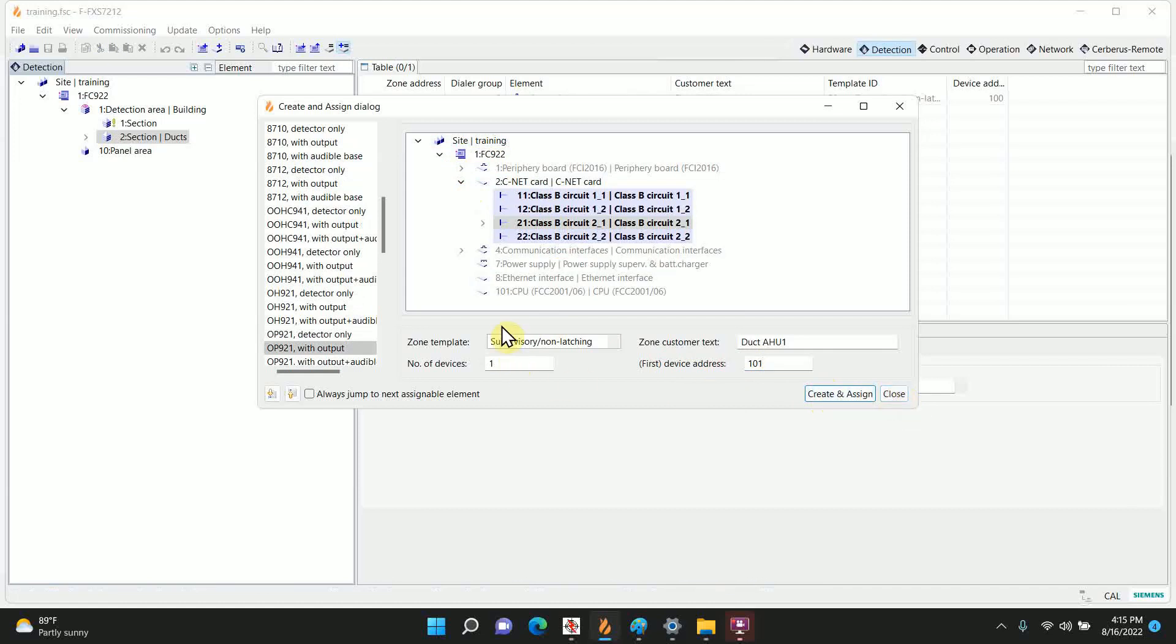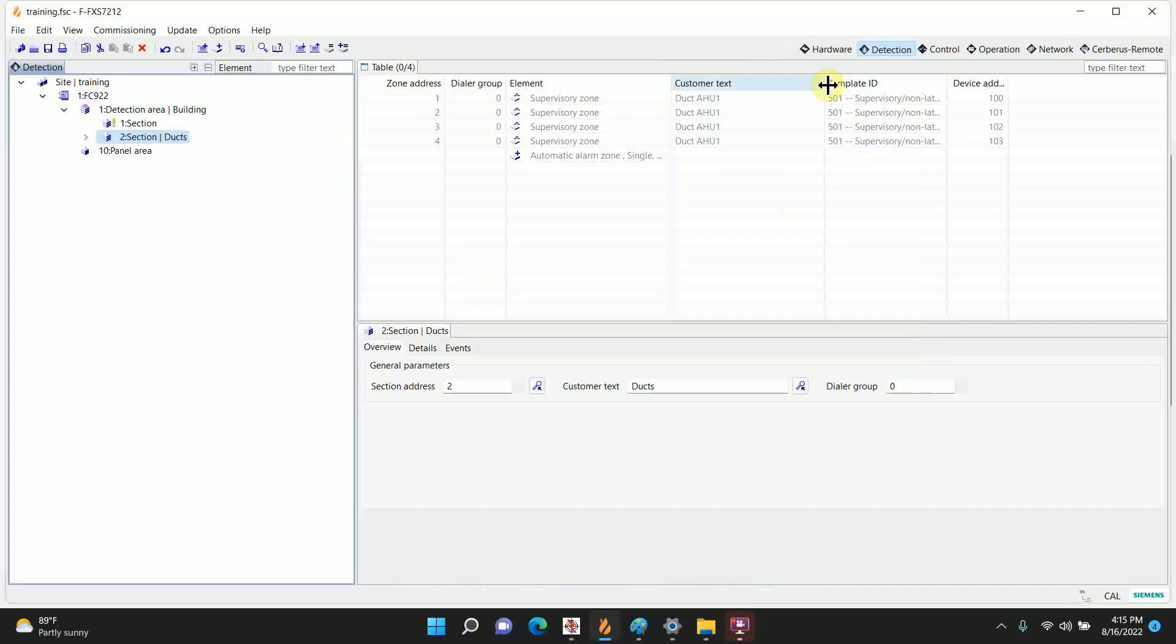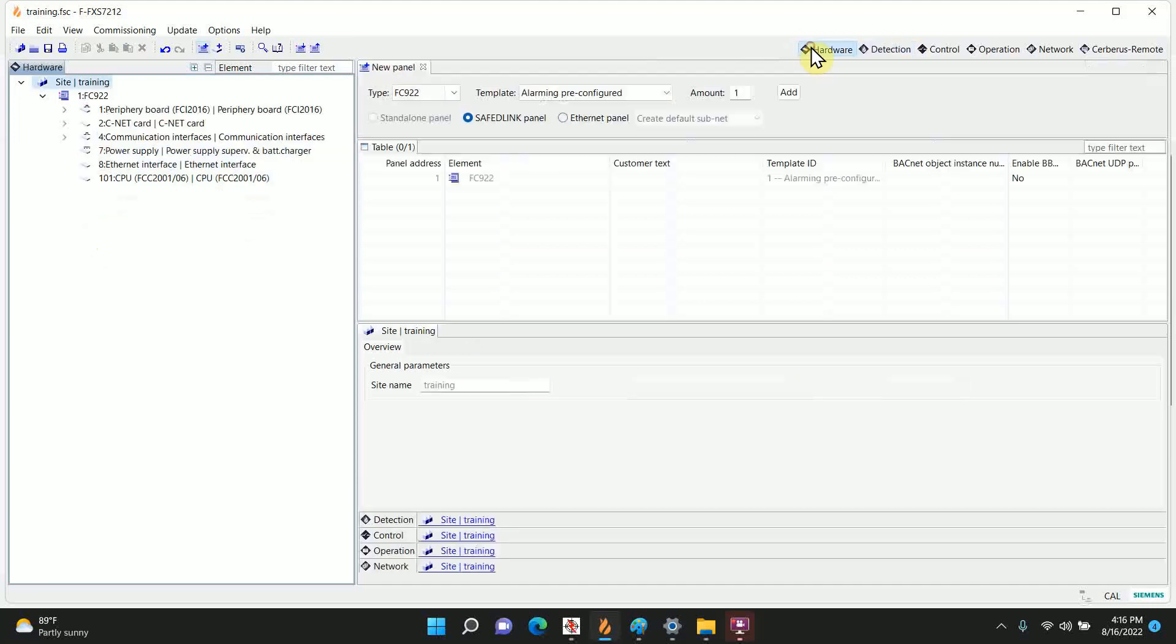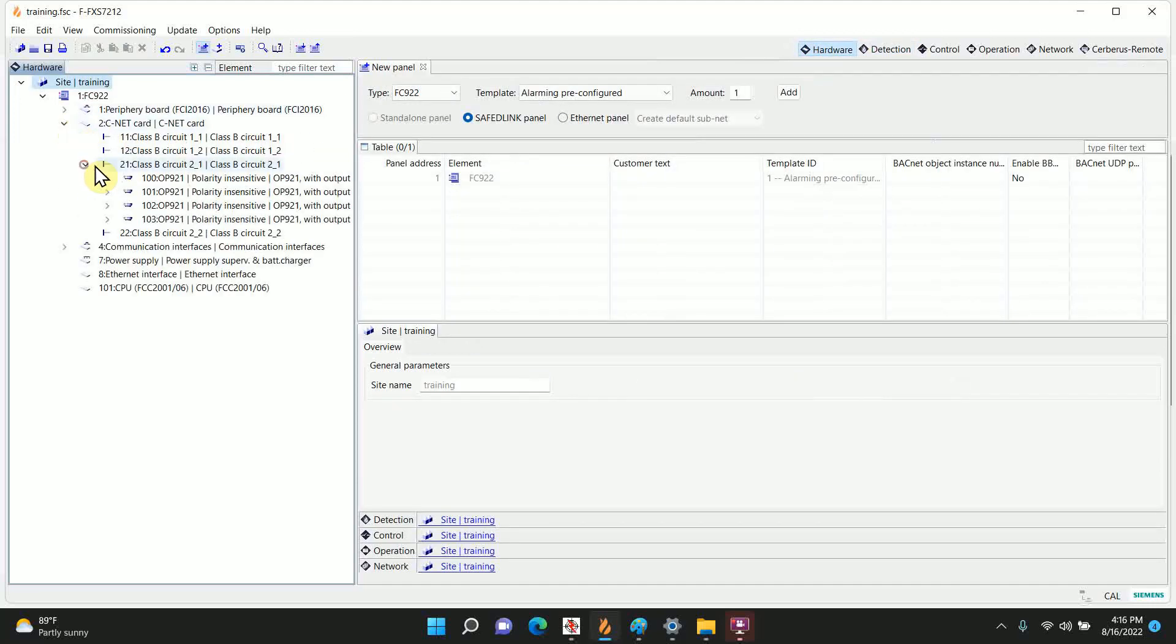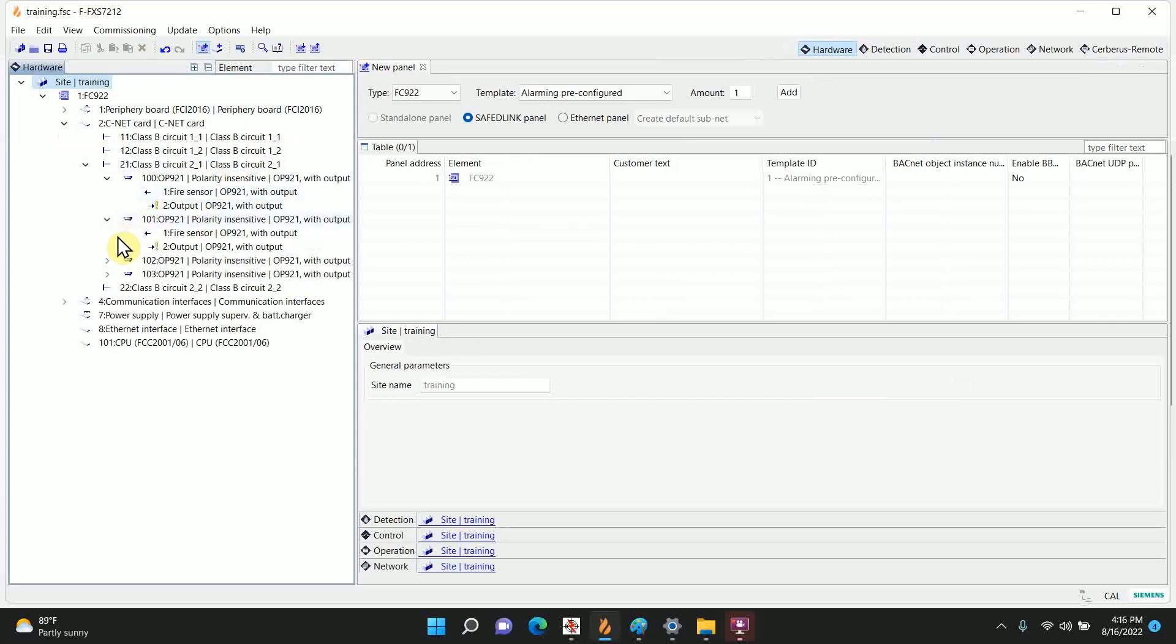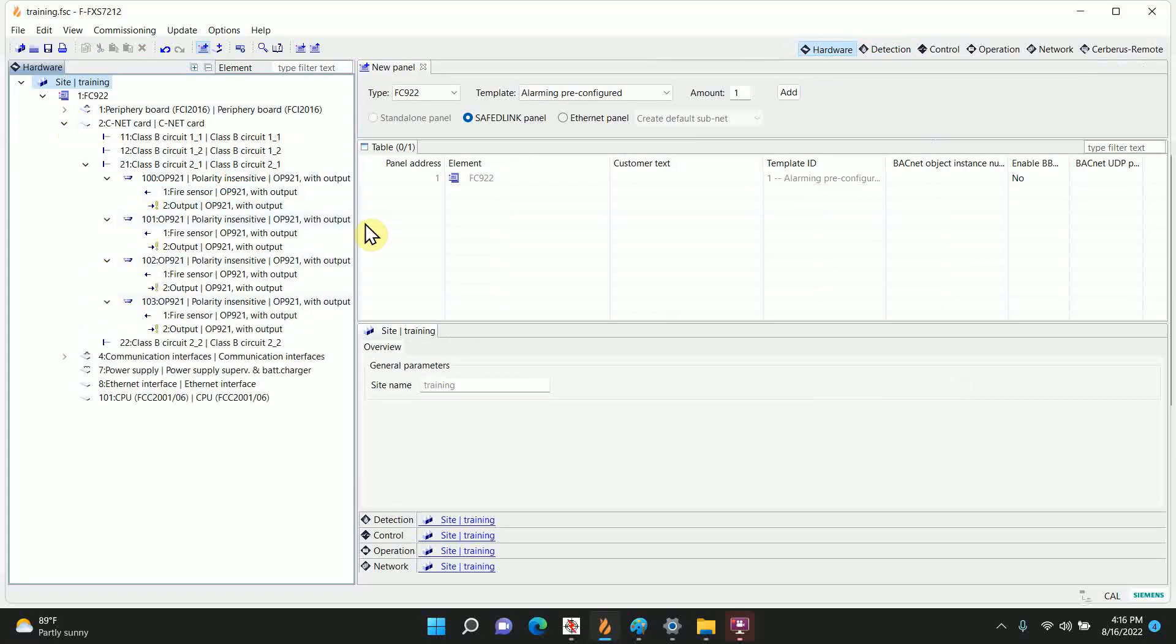It only did one device, changed it when I changed it on the hardware. So we're going to add the other three now. Create and assign, OK. Now with that, let's go ahead and open it up, you can see what it did. It has made four supervisory zones all called duct air handler one and they all got the smoke in there. Go to the hardware tree, you open it, see that? We stuck it in 2-1. You can see it added one and there's the output. And if you notice, the output has the yellow exclamation point. That means it's there but it's not assigned. So at this point, nothing will ever trigger the output or the relay on your duct detector housing.